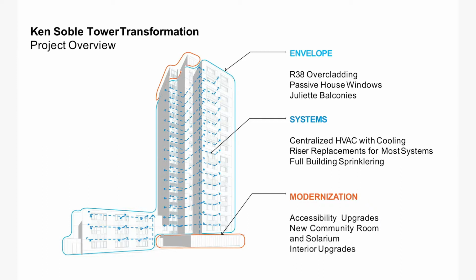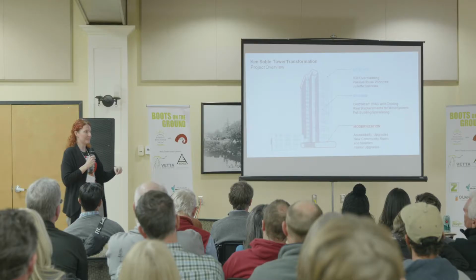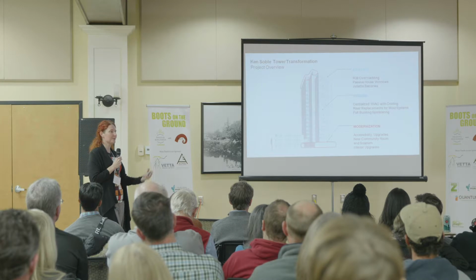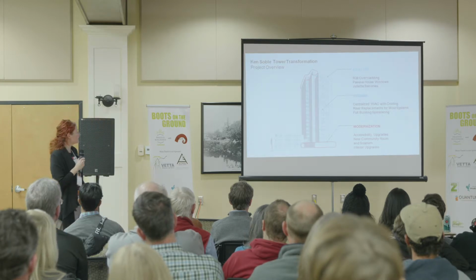At the mechanical level, we're doing a centralized HVAC system with cooling, with a high-performance ERV located on the roof. The reason we went that way is that the building in its current form has shafts which contain both exhaust and supply, serving all of the suites already. So instead of having to make another 300 holes in the building envelope, we decided to try and go centralized.